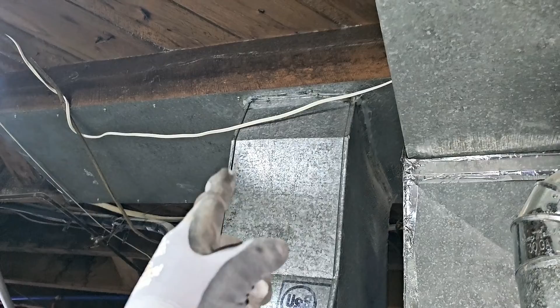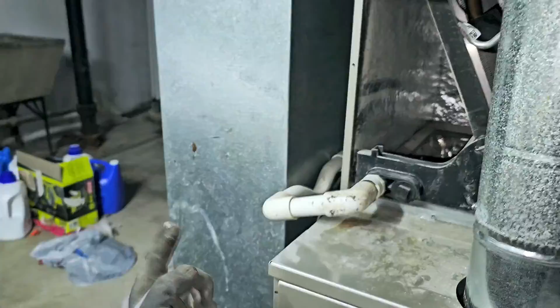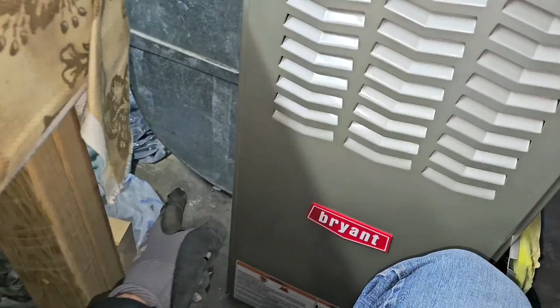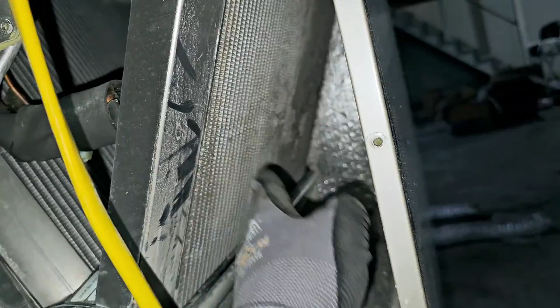I asked the homeowner why this coil was so dirty, and they said that when they moved in, there was no filter upstairs, and that's where the return box goes, and there's a 20 by 20 return and a 20 by 20 filter. They've got a filter in there, so they're being responsible. They're taking care of the filtration, but when you don't have a filter, the dust that comes from the house goes in the return, goes in the side of the furnace, goes up through the supply, goes through the coil, and it gets in there.